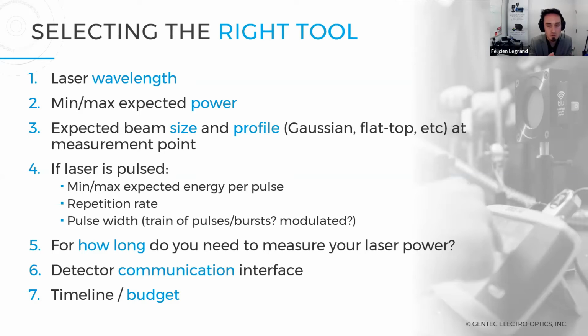Then, for how long do you need to measure your laser power? Once again, is that just a single-shot power? Just, okay, I'm at 25 watts for 5 seconds, that's all I need to know. Okay, I'm at 4.5 kilowatts, and I just wanted to be sure I'm at the right range. And you want to measure that for a couple of seconds, or do you want to see a drift in power and you want to measure for hours, for days, or for months, for developing new sources, for example?